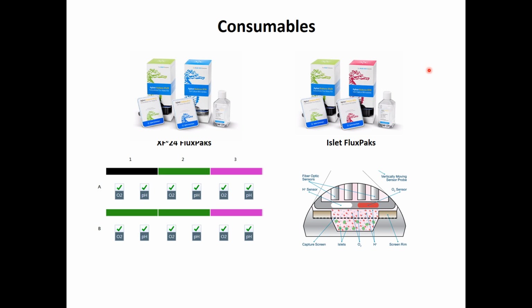This system needs consumables to make sure the whole system is stable. So you need to use the certain cell culture plate, and if you do the tissue sample, you need to purchase the islet capture microplate. And the fluorescence sensor cartridge is in a green package, and here is the calibrant solution to hydrate the fluorescence sensor. The fluorescence sensor is kept stable in dry condition, so we need to hydrate it one day before assay.